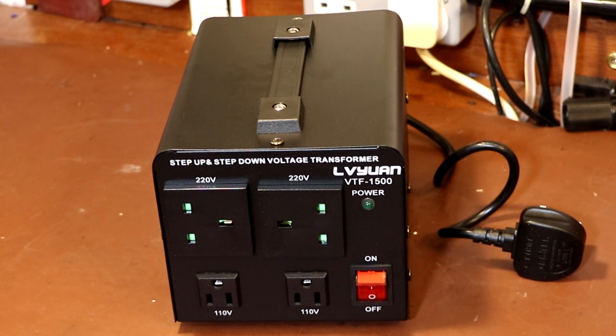For many types of equipment the difference between 50 and 60 Hz won't make any difference. A transformer doesn't care, it will work just as happily at 60 Hz as at 50 and vice versa. But there is equipment, maybe things that contain electric motors, synchronous motors or fan motors, where this matters. For example, if you bought a clock from the United States, it would be designed to be locked to the line frequency, which is 60 Hz. So if you run it at 50 Hz, it's going to run slowly.